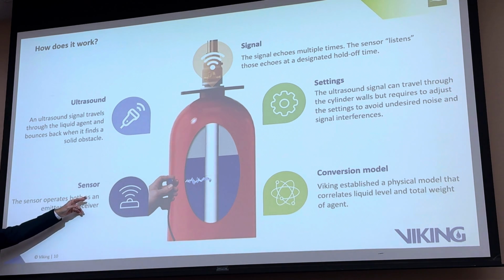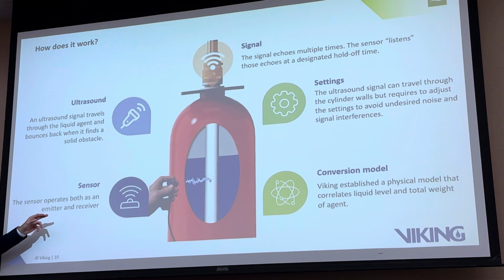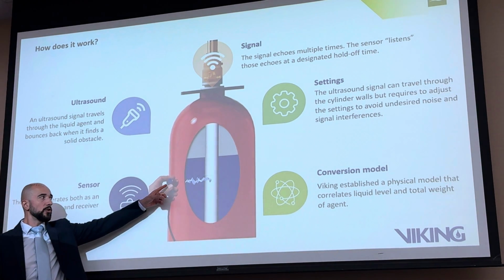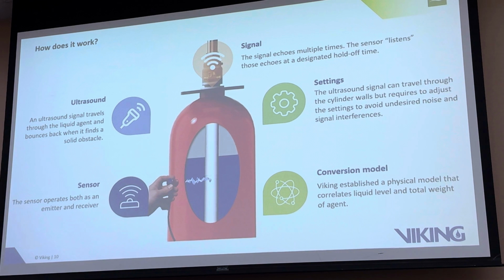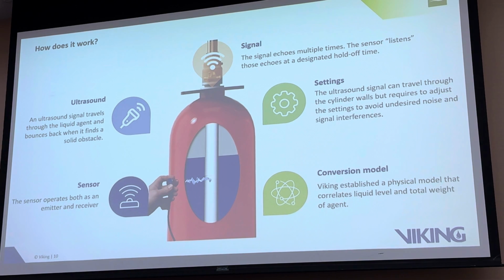There's a sensor that operates both as an emitter and as a receiver - this small handheld piece that emits and receives the signal. It works with ultrasound - that's the signal it emits, which travels through the walls of the cylinder, through the liquid, reaches the siphon tube, and bounces back. Depending on the time elapsed from emission until it returns, it can identify if there's agent present and what agent it is. So the signal echoes multiple times, and this device has the ability to recognize if there is liquid and what liquid is there.